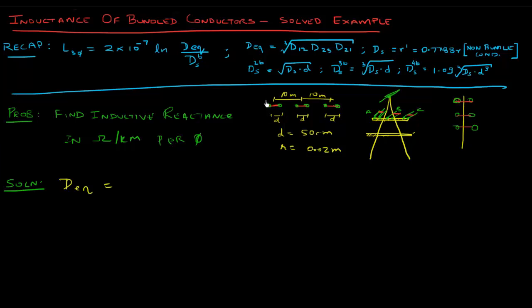Let's first find out the equivalent, that is d1 to 2. This is in essence 1, this is 2, and this is 3, right? So d1 to 2 is 10 meters, d2 to 3 is again 10 meters, d3 to 1 is 20 meters, and cube root of that. If you plug that into our calculator, should give us something like 12.6 meters.